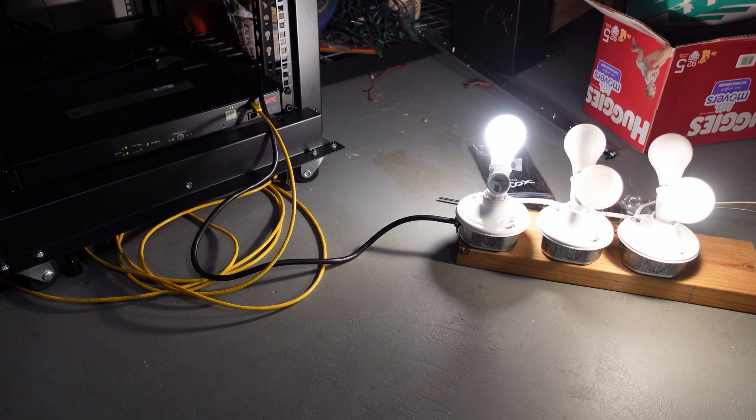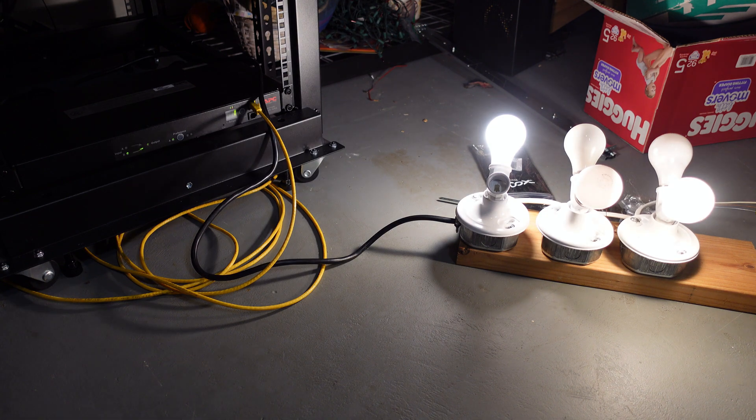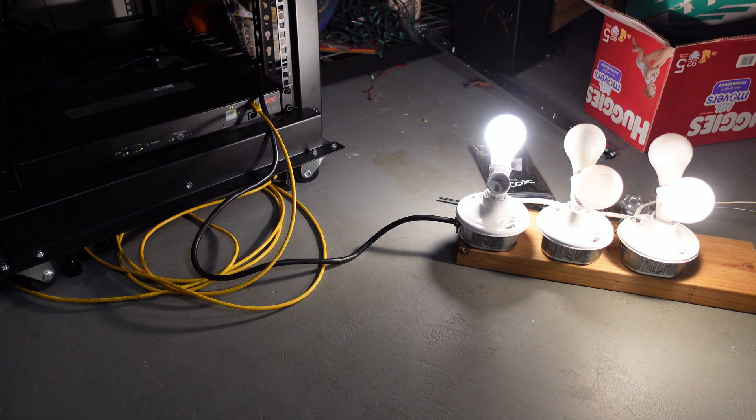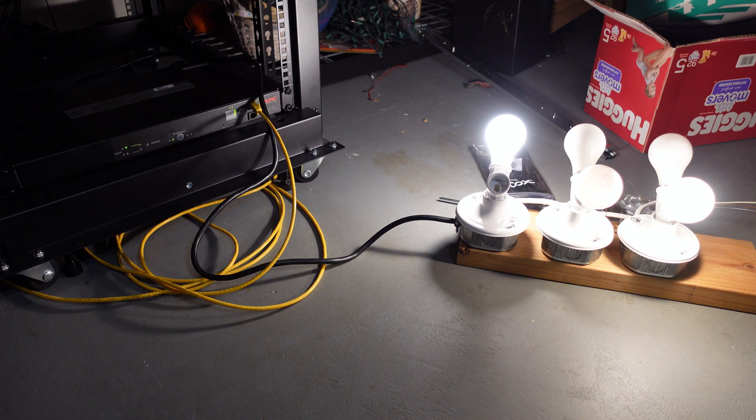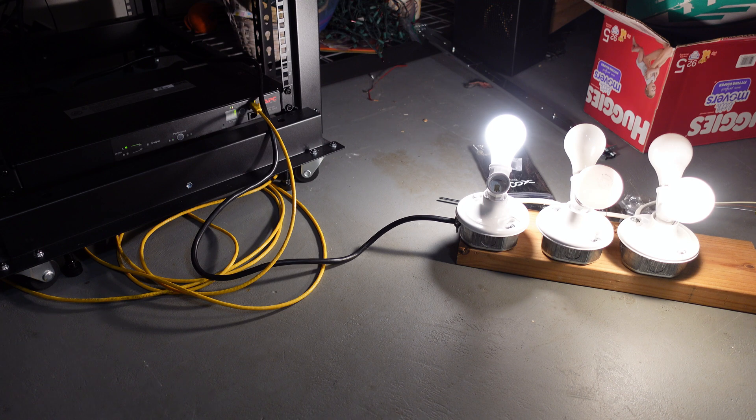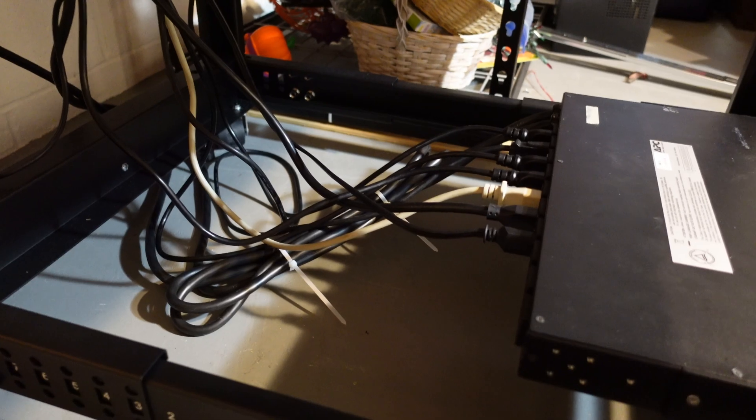All right, so I'm going to unplug source A, and you can see it switch to source B. I'm going to plug back in source A. Now I can unplug source B, and you see it switch to source A. So it does appear to be transferring correctly, and it does appear to be transferring fairly quick. We just see a slight dim of the light bulbs.